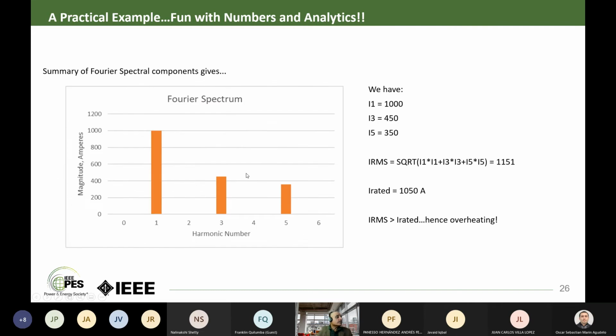Let's look at the summary of the Fourier series. I1 is 1000, the RMS value of the fundamental; I3 is the RMS value of the third harmonic; I5 is the RMS value of the fifth harmonic. If I look at I_RMS, this is 1151. Our rated current from the nameplate is 1050. This is greater than that, so we have overheating.